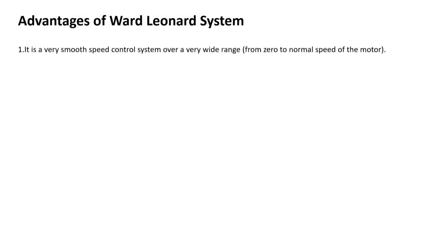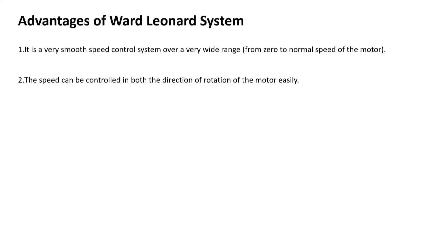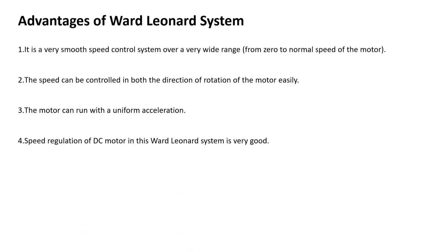The advantages of the Ward Leonard method are: it provides very smooth speed control over a wide range; the speed can be controlled in both directions of rotation of the motor easily; the motor can run with uniform acceleration; the speed regulation of the DC motor in this system is very good; and it has regenerative braking property.